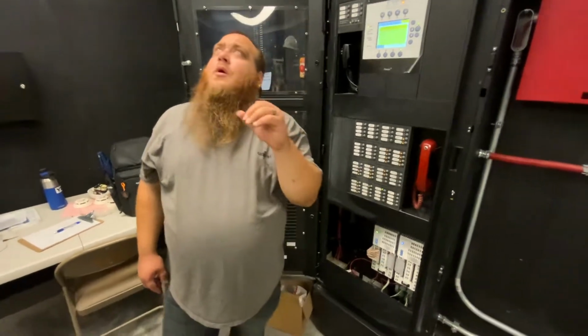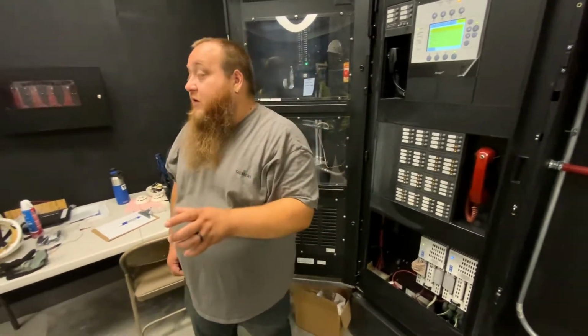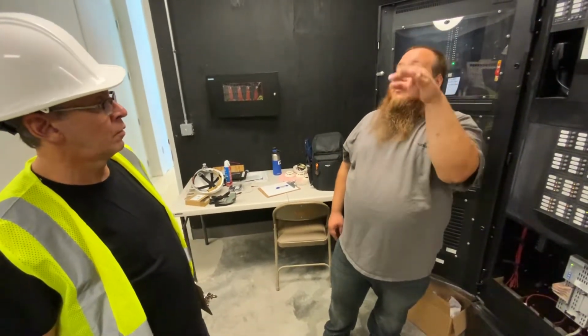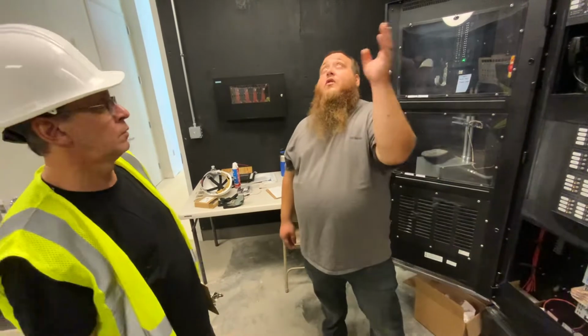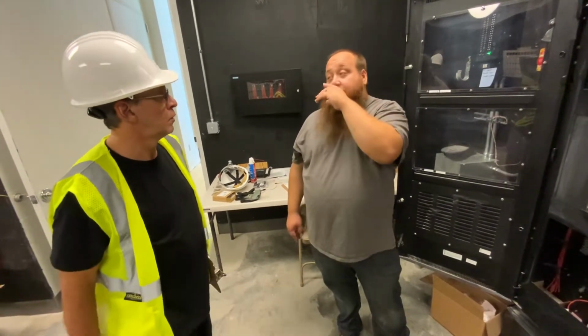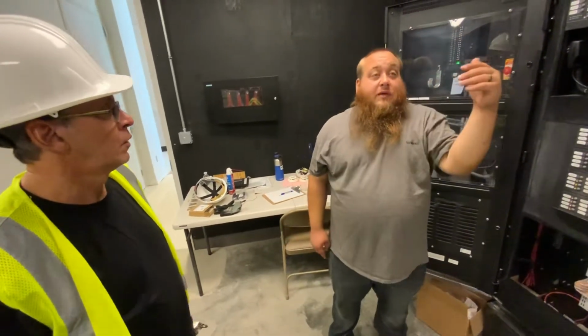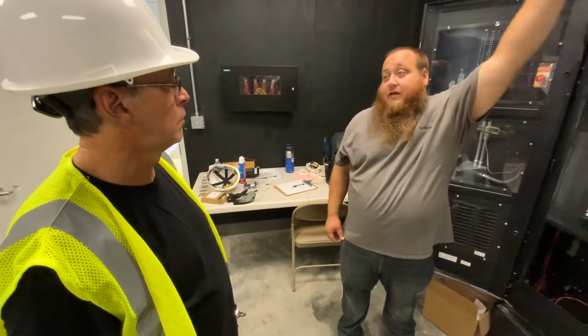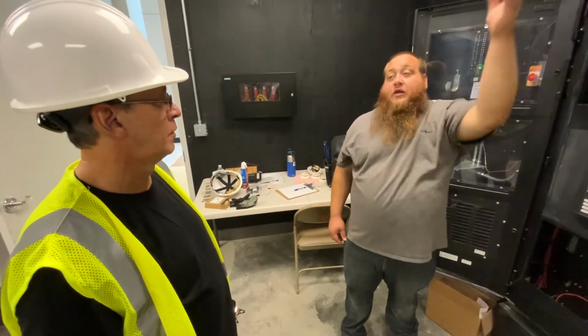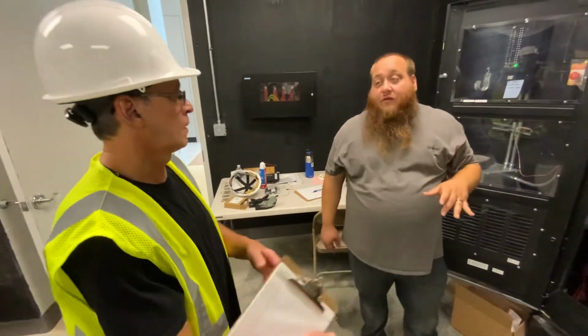No problem. Now, with all these devices, they'll have a sticker identifying its device number. The first number is its loop number, and the second number is its actual physical device number. So whenever you're in an area, make sure you get both numbers, because there are 8 device cards in here, so technically there could be 8 '50s' out there. But it'll be labeled 1-50, 3-50, or whatever, so you know you have the right device.